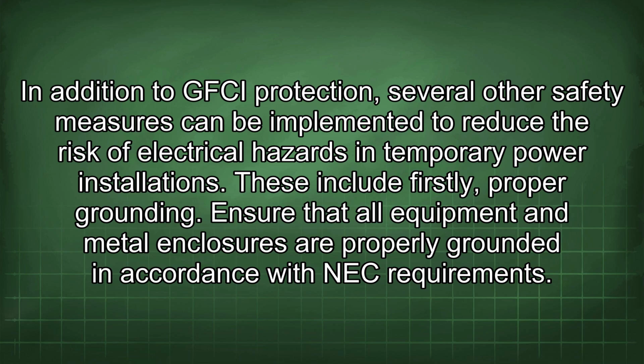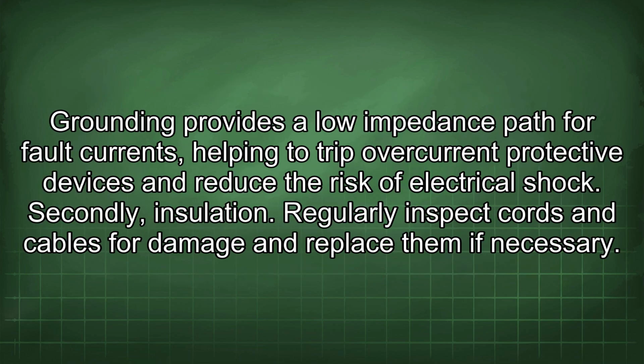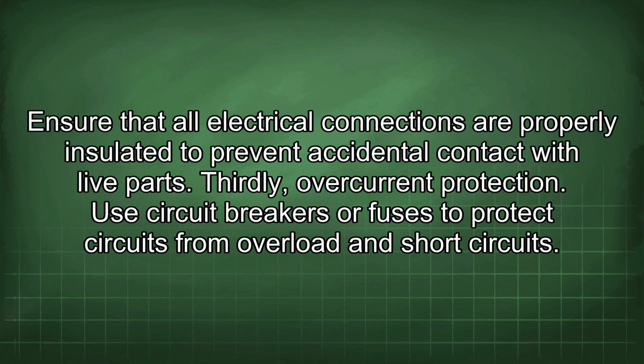In addition to GFCI protection, several other safety measures can be implemented to reduce the risk of electrical hazards in temporary power installations. These include, firstly, proper grounding. Ensure that all equipment and metal enclosures are properly grounded in accordance with the NEC requirements. Grounding provides a low impedance path for fault currents, helping to trip overcurrent protective devices and reduce the risk of electrical shock. Secondly, insulation. Regularly inspect cords and cables for damage and replace them if necessary. Ensure that all electrical connections are properly insulated to prevent accidental contact with live parts.